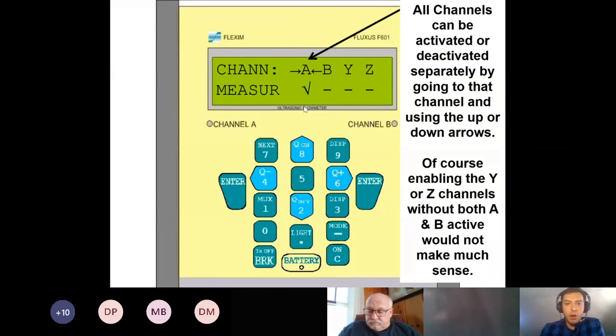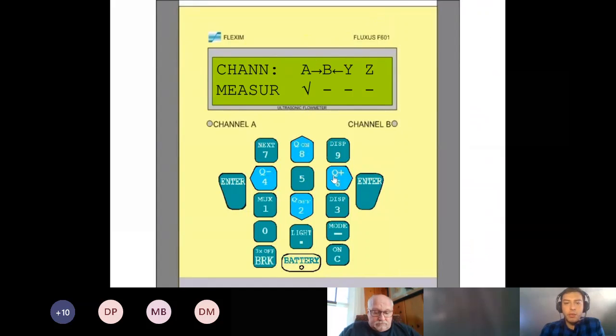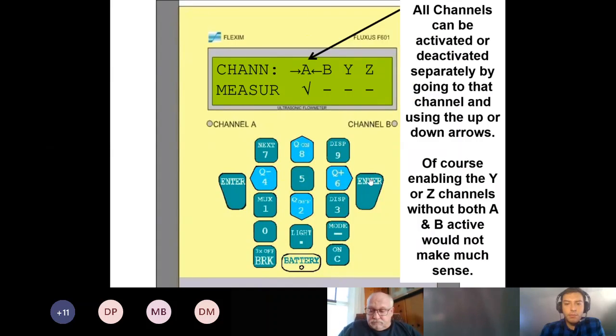So you make sure you have channel A marked because that's where my transducers are plugged in. If you have channel B, you use the 4 and the 6 to move left and right, and you hit the 2 to turn it on and off. So we're just going to do A. For those of you who don't know, channel Y and channel Z are math channels. So you can either do channel A plus channel B, you can do channel A minus channel B, you can do an average of the two to get a better flow profile. There's a lot of different things you can do with those channels Y and Z.